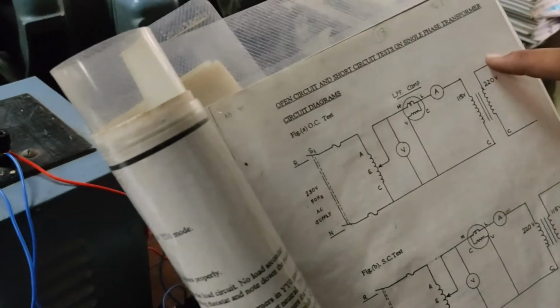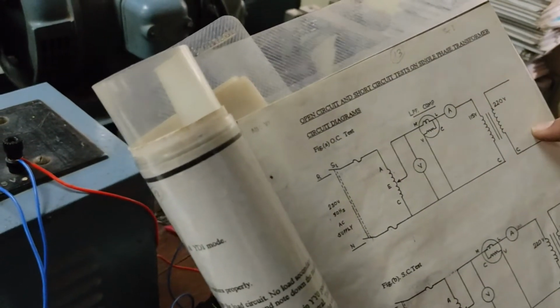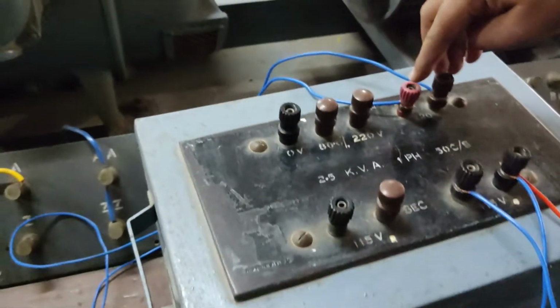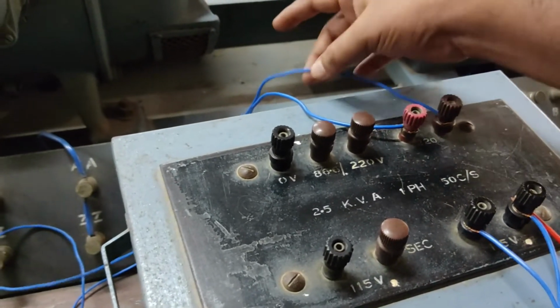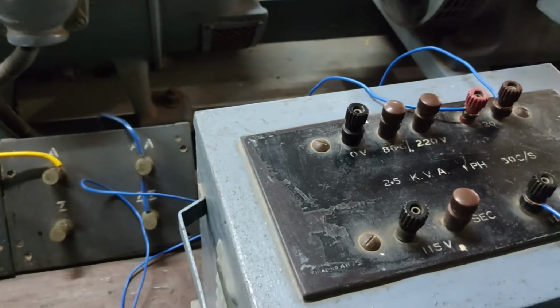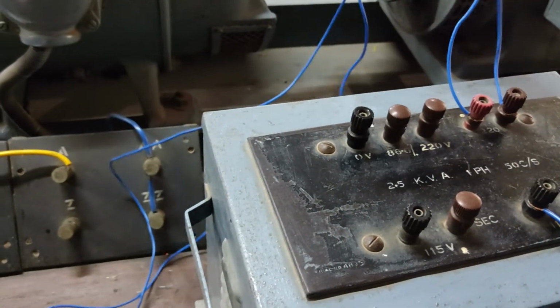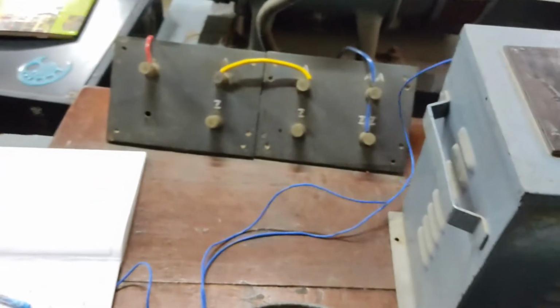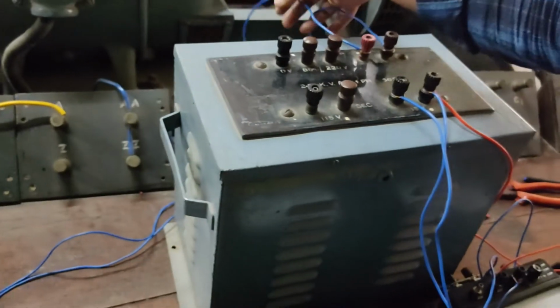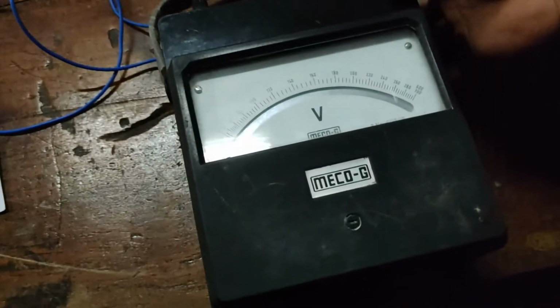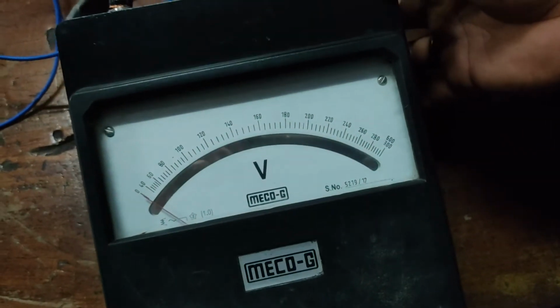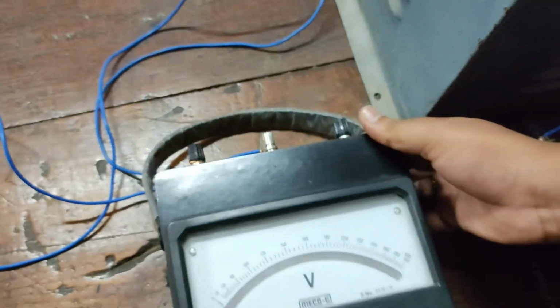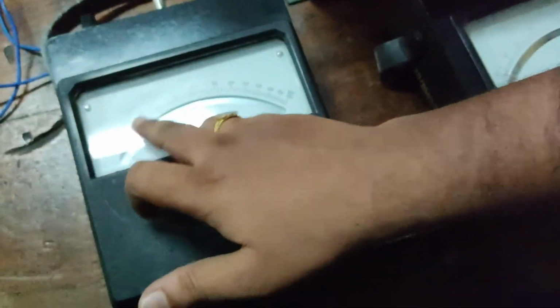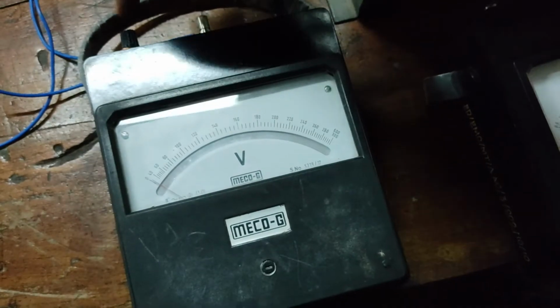After that, for the OC test, the high voltage side should be open. This is the high voltage, the 220 volt output of the transformer. It is open circuited, so we have not connected any ammeter or voltmeter. We have connected a voltmeter only to measure the output voltage in the open circuit condition, to see how much voltage it shows when we give the input voltage of 115. We connected a 0 to 300 volt range, but we require only 220 volts. That's why this range is selected. These two terminals we have used.